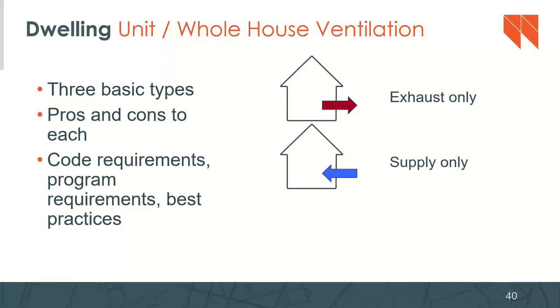The second common one is supply only. It's the same thing as exhaust only in that it's running 24/7, or running intermittently and automatically on a timer control, but it's pushing air in. It's bringing outside air into the structure. With exhaust only, the space is negatively pressurized with reference to outside. With supply only, your house is positively pressurized with reference to outside. The third one is balanced, which is the Passive House preferred, high performance version. You're doing both supply and exhaust at the same time. It's referred to as balanced because the space inside your home is neither positively nor negatively pressurized with reference to the outside. At least that's the idea.